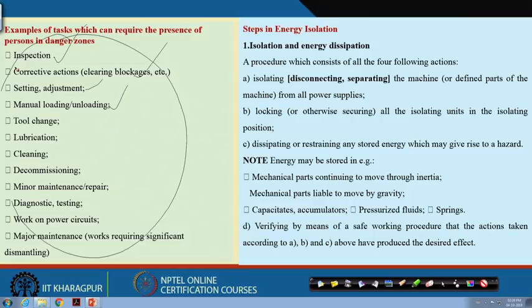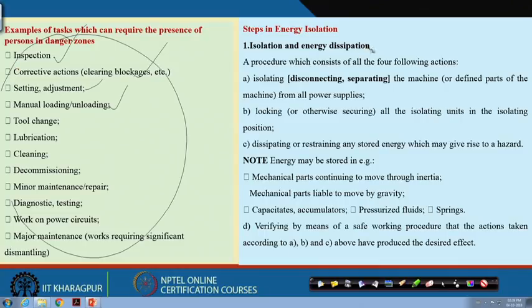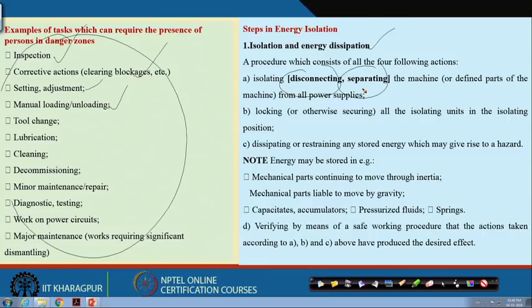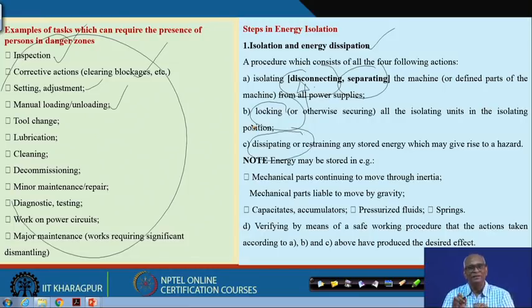When you have to do all these things, you are in the danger zone. If you want to do the job and not be harmed in the danger zone, it calls for isolation. Isolation is disconnecting and separating — two activities: disconnecting and separating. In lockout and tagout there is only disconnecting; in isolation there is disconnecting and separating. Then you put the lock and you dissipate the energies.